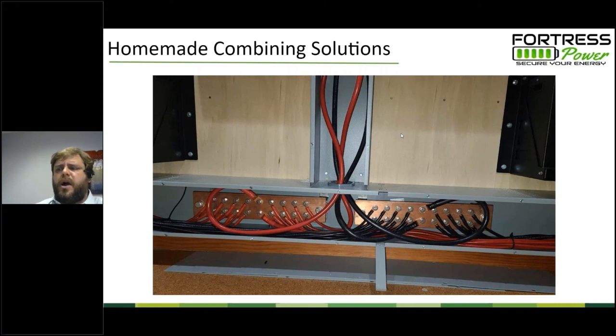This is a common issue with our eFlex battery, which is a smaller battery. If you're installing multiple batteries, you have to wire them together, or our larger residential or commercial customers may be paralleling a bunch of eVolts together. This solution is a bus bar inside a gutter. I can tell you that this solution is common and that it works, but you might be thinking, is it going to pass inspection? It really depends. A bus bar inside a gutter is in an enclosed raceway. You are allowed to put bus bars inside of gutters.